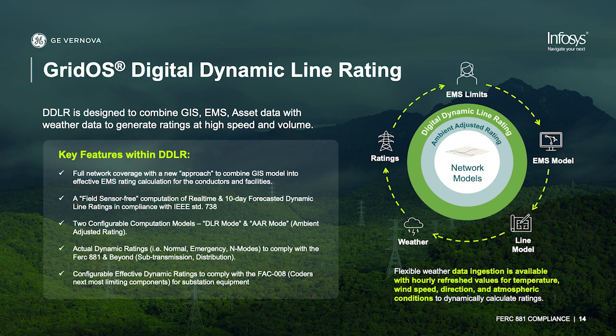In addition, by going to a digital dynamic line rating, you essentially unlock dynamic line ratings for your entire footprint without installing a single sensor, and you future-proof your system because FERC has already moved on to doing an inquiry on using dynamic line ratings across the grid. So you'd essentially future-proof your system by installing a digital dynamic line rating application.